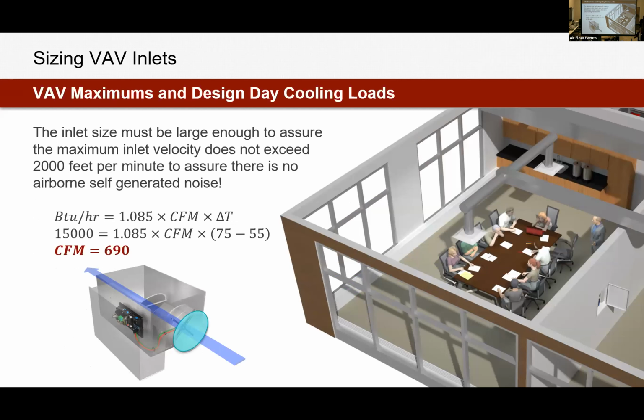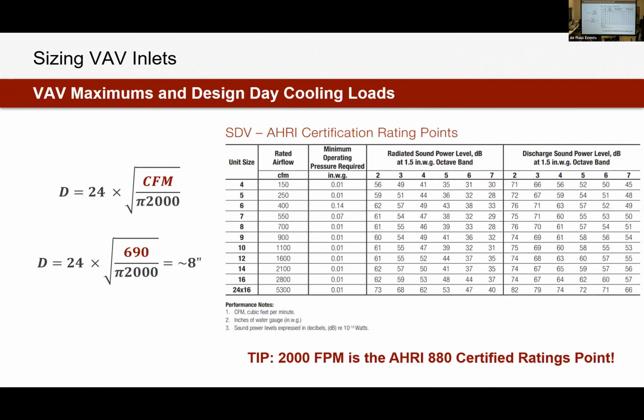So with this simple heat transfer calculation, if you're an engineer, you've probably seen something like this before. We know what our load is in the space. We know our target delta T. So what is that resulting airflow? Through this equation, we can see that our airflow is about 690 CFM. And we always want to be sizing the inlet valve to result in a velocity no greater than 2,000 feet per minute. 2,000 feet per minute is the threshold for where an inlet will start generating its own sound. So we have our airflow, but we want to pick an inlet size that keeps us less than 2,000 feet per minute. With a little bit of circumference or area calculations, with that determined airflow, we can see that an 8-inch inlet valve would keep us below the 2,000 feet per minute set point.